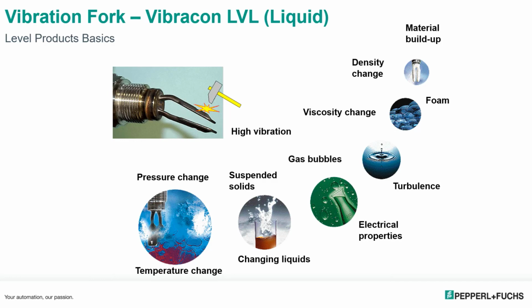They're pretty resilient against pressure changes and suspended solids. Viscosity changes, density changes, and like we saw, material buildup and corrosion on the probes themselves. Turbulence too. It seems to be pretty good with all of these types of changes in your liquids.